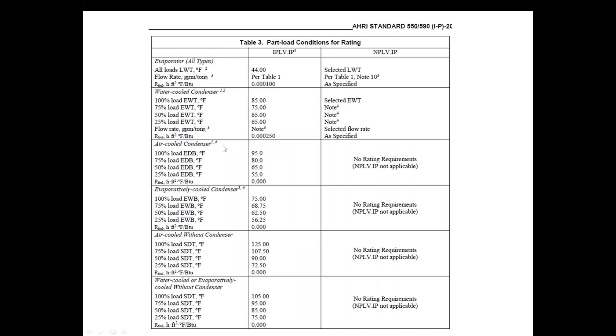This part load performance — IPLV and NPLV — is calculated based on AHRI standard 550/590. This standard covers various types of chillers: water-cooled condenser, air-cooled condenser, and evaporatively-cooled condenser types. Based on the type, IPLV follows the standard and NPLV is non-standard. The detailed procedure for conducting the IPLV test can be obtained from the AHRI website under standard 550/590.